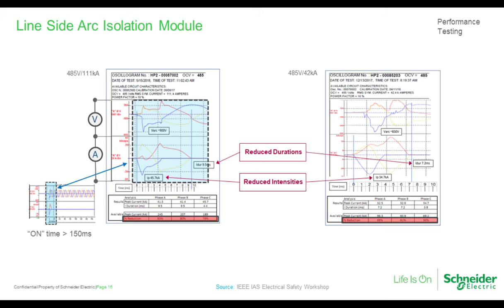These tests were both run at 480 volts, and the test on the left is at 111,000 amps available, and the one on the right is at 42,000 amps available. A few things to note. First is the test station was on for 150 milliseconds, more than 9 cycles. But the arc durations themselves were less than 10 milliseconds, less than 1 cycle. In other words, the ArcBlok device cleared the fault in less than a cycle and carried the open circuit voltage for the 8 remaining cycles, just like a circuit breaker.